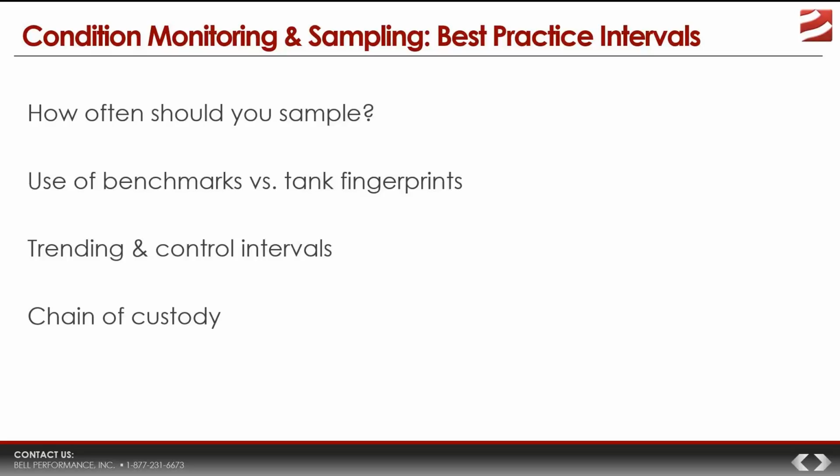I mean, absolutely not. You do not have to sample every day. The best practice, most common thing that a microbiologist would recommend is that you sample 3 times during your control interval. Okay, control interval. We're throwing another term into it. What's a control interval? Well, the control interval for your particular system is the length of time that your tank takes to develop problematic levels of microbial growth.